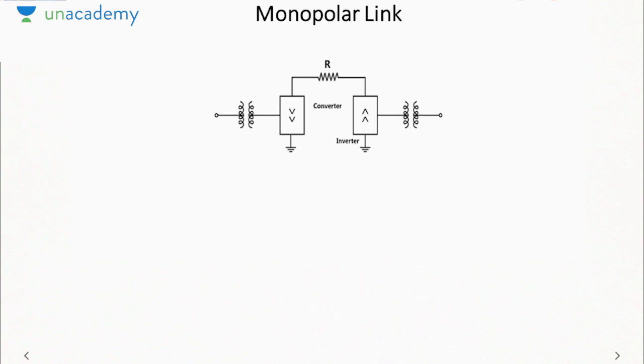Now there are various types of DC links. First is called a monopolar link. So as we know, for power transfer or for current flow, we need a closed circuit. Either the closed circuit can be done by means of two wires, one as a forward conductor, the other as a return conductor, or you can use only one conductor and the ground as the return path. So here we are using ground as a return path and we use only one conductor.